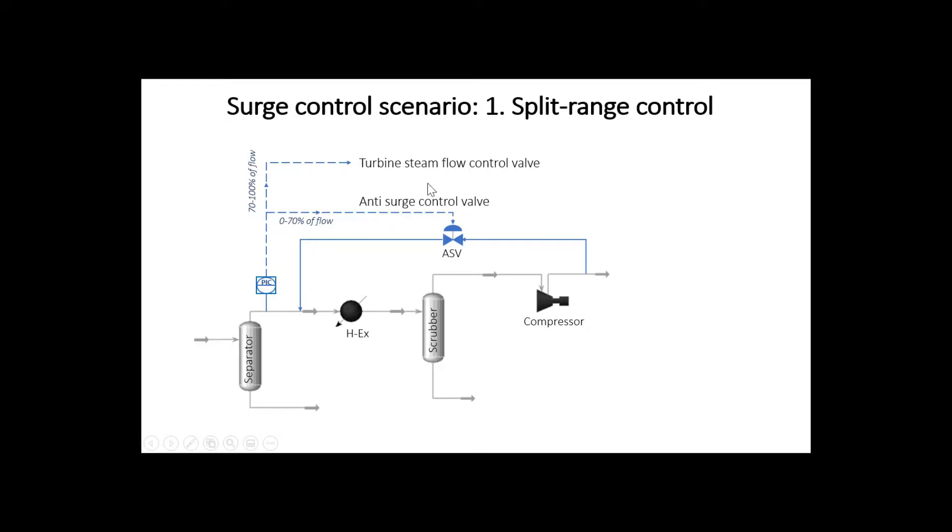If the pressure further decreases below 70%, then control system additionally opens the anti-surge valve and recycles the discharge fluid in order to pressurize the suction line. This is one example where we employ split range control in anti-surge control system.